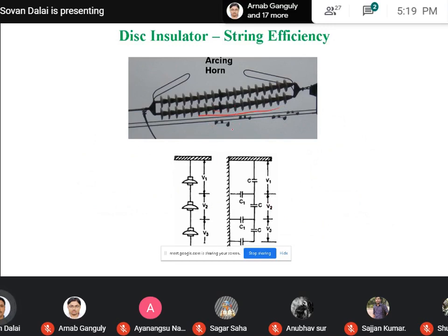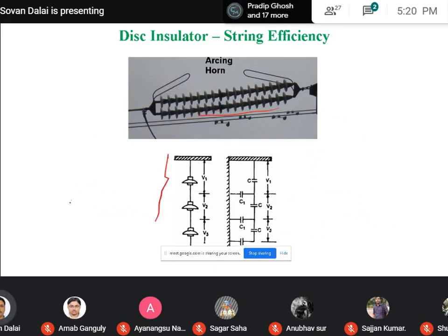There are two types of orientation. One is called horizontal orientation, another is called vertical orientation. Again, if you connect the insulator in that fashion, there is a tower. With the tower, some distributed capacitance is formed with the discs of the insulator. That is basically called the earth capacitance. Due to the formation of this earth capacitance, the voltage distributed across the different discs will be different. The disc nearest to the line conductor is subjected to the highest voltage, and if you gradually proceed towards the earth, that voltage level gradually reduces.